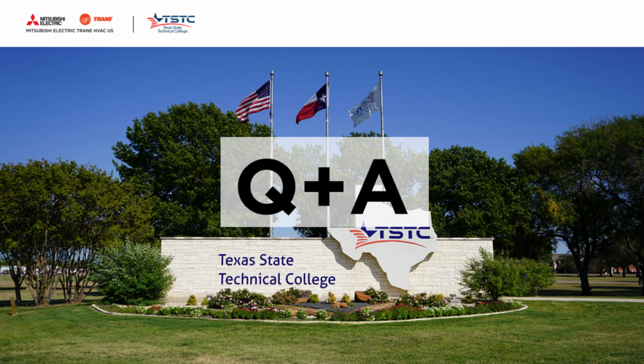Excellent. Now, just a short addendum to that, because it's a question a few people ask. Can VRF be integrated with a BAS? Yes, absolutely. Any size and scale of a VRF system can be integrated to any of those control brands I mentioned, and there are two things I'll point out. Number one, for any brand of VRF, when you are integrating it to any brand of controls, let's pretend that an indoor unit in Office 101 has 90 different control points, 90 different data points. Any controls integration to a BAS, a BACnet system, the integrator is going to need to choose from those 90 points and write a custom integration for however many end up being chosen. If they say, okay, we really need these 30, then those 30 need to have an integration written for them.